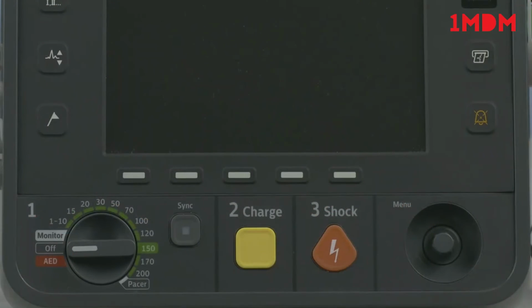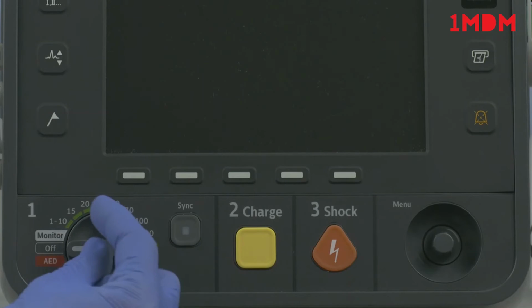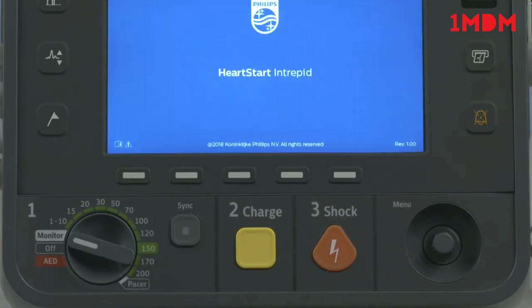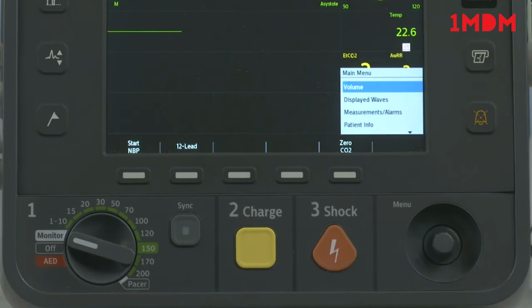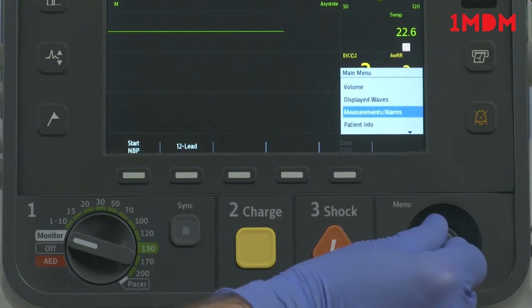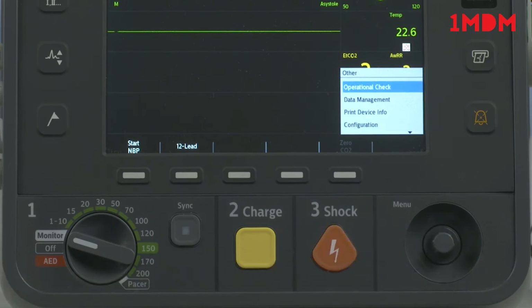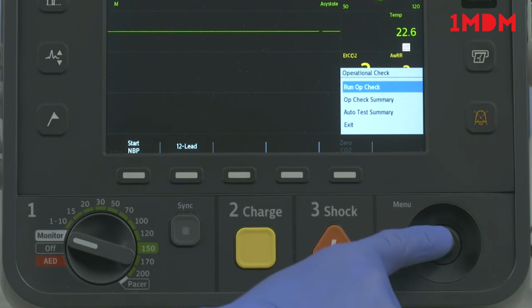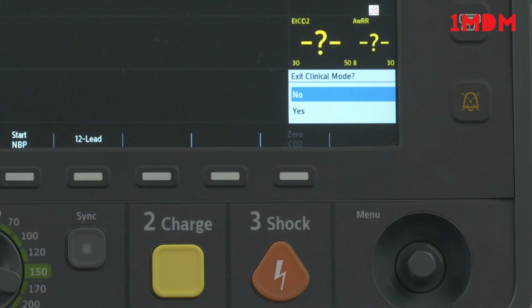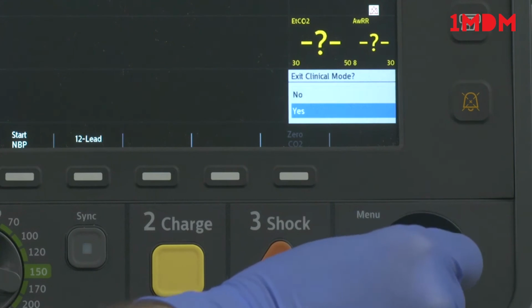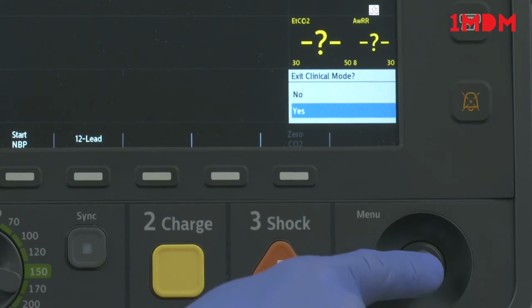To perform the operational check, turn the therapy knob to Monitor. Then press the Smart Select knob. Using the knob, select Other, Operational check, and Run Op check. This message lets you know you are exiting from all clinical functionality and entering a test mode. Select Yes to leave clinical mode. Then press the Smart Select knob to start the check.